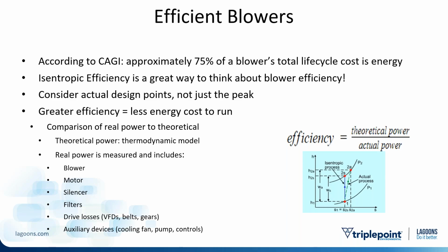That theoretical data is going to come from any number of government websites or guides widely available in the public domain, or from the manufacturer or whoever you're working with as a representative talking about blowers. They'll provide that data. But real power is measured, and that's going to include everything else plus that motor - the blower, the motor, silencer, filters, drive losses.